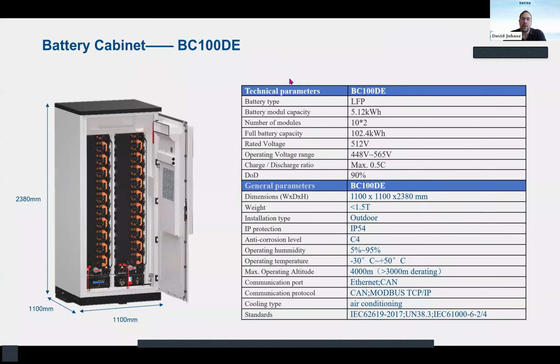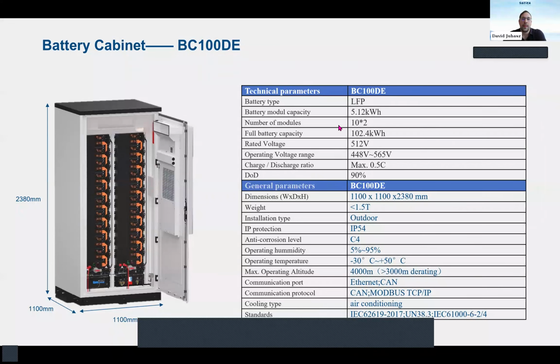Regarding the data sheet, some important points to mention: one module's capacity is 5.12 kilowatt hours, and the number of modules is 10 times 2, so overall it's 20. The rated voltage of one cluster is 512 volts, and the maximum depth of discharge is 90%.